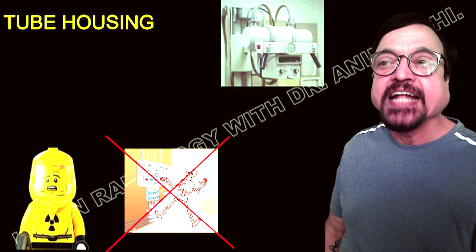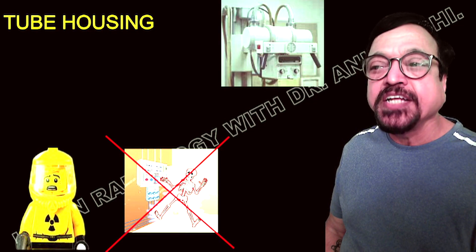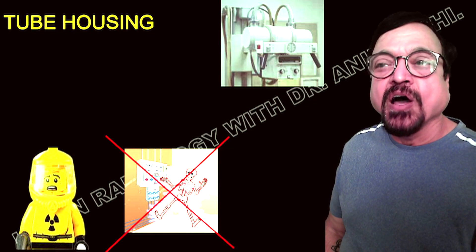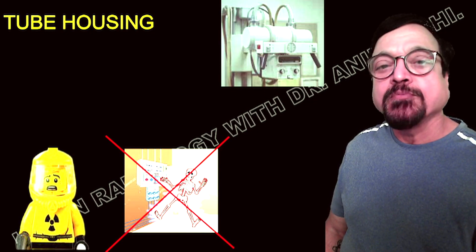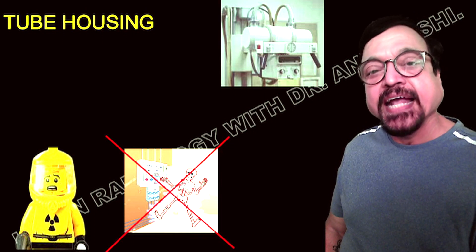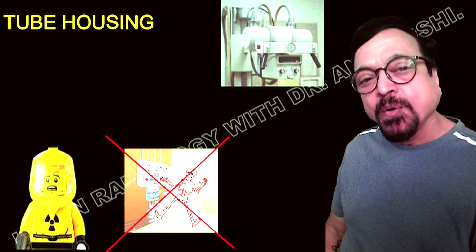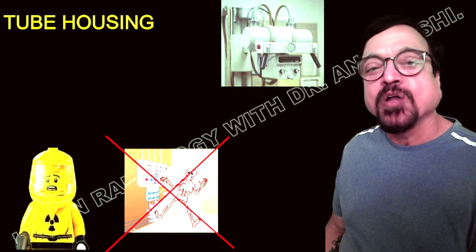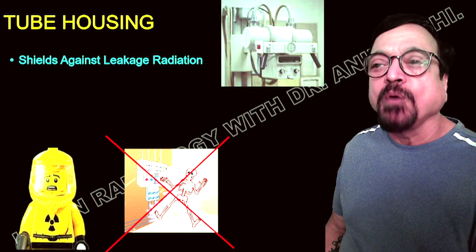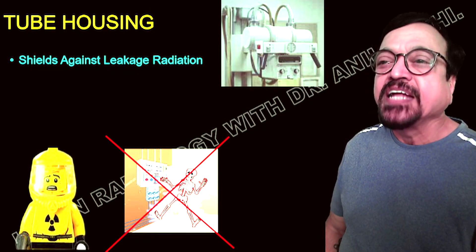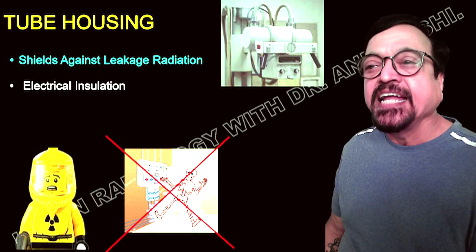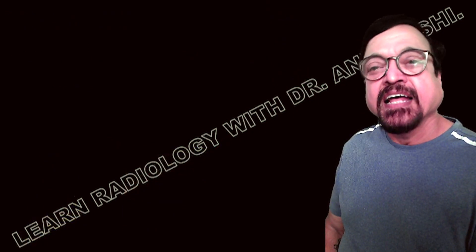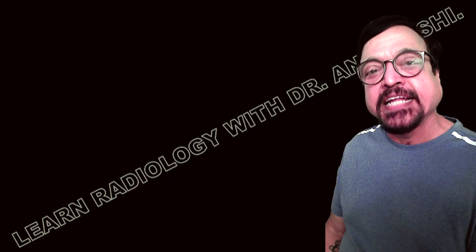The tube housing is the outer layer. Its main aim is to protect what is inside, since high voltages are transferring from anode to cathode and x-rays are being produced. The housing does two things: it protects you, and it allows x-rays to exit in a specified area which can be collimated, restricted, or filtered. So the tube housing is a shield against radiation leakage and also acts as an electrical insulator.